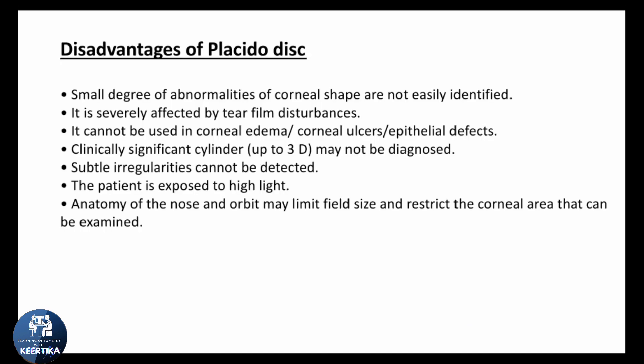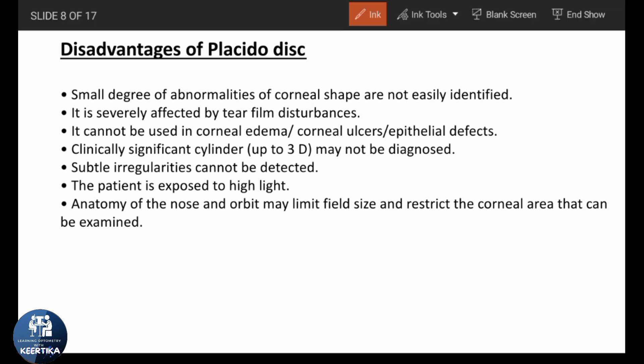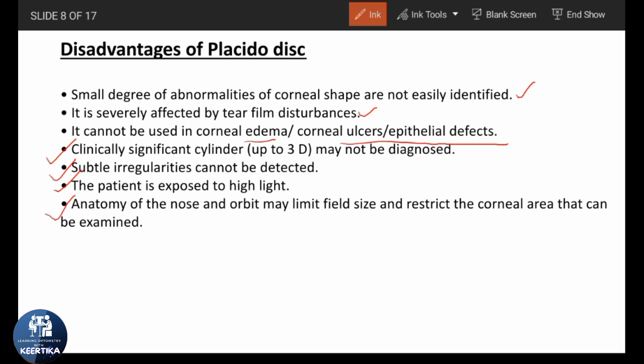In spite of its advantages, Placido disc has many disadvantages. Small degrees of abnormalities in corneal shape cannot be easily identified. It is severely affected by tear film disturbances, since the reflections come from the tear film — in patients with poor tear film, distorted mire will not give correct information about anterior surface curvature. It cannot be used in corneal edema, corneal ulcers, or epithelial defects. Clinically significant cylinder up to 3 diopters may not be diagnosed. Subtle irregularities cannot be detected. The patient is exposed to high light during the procedure. Additionally, anatomy of the nose and orbit may limit field size and restrict the corneal area that can be examined.